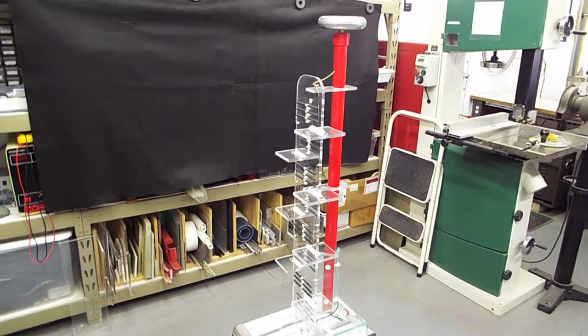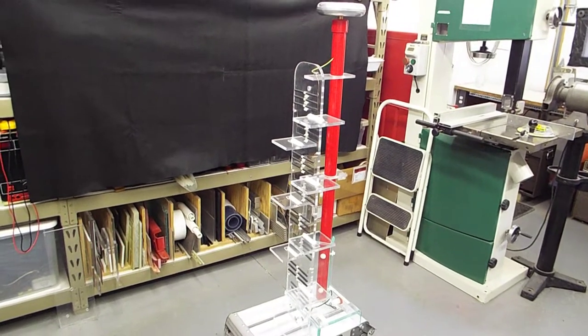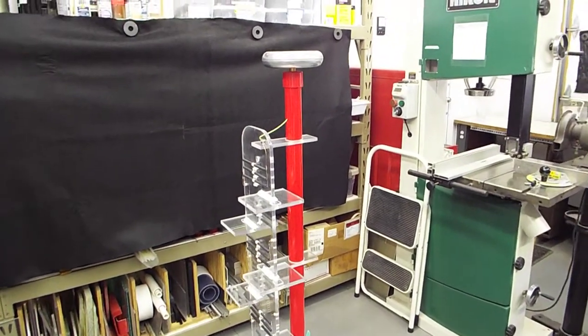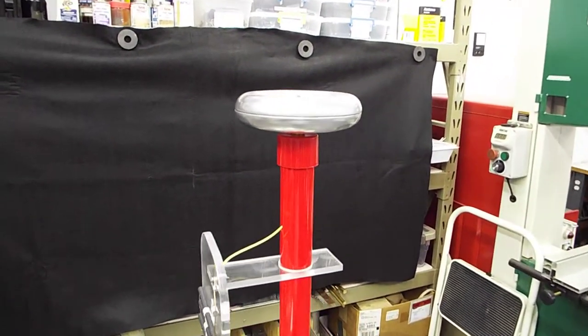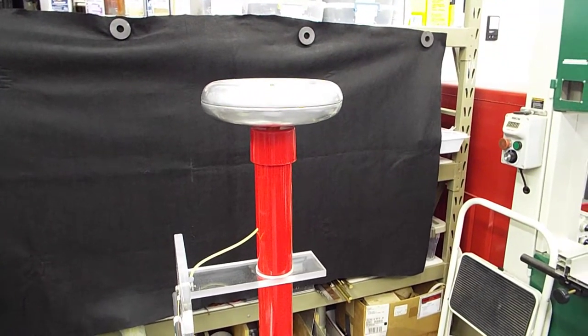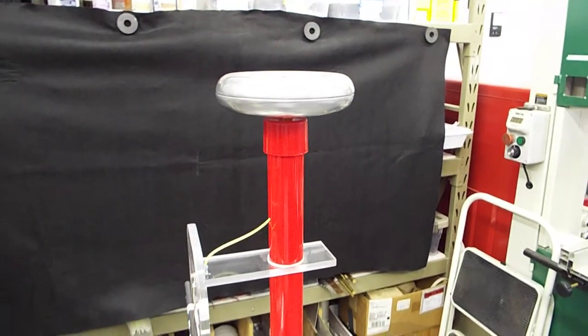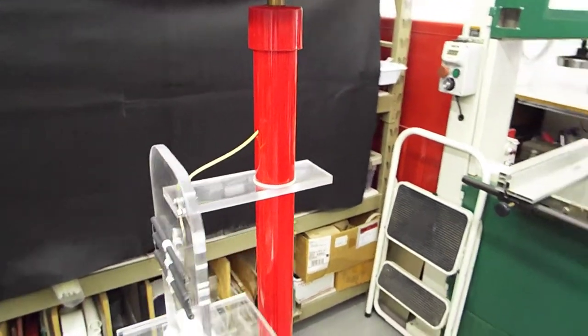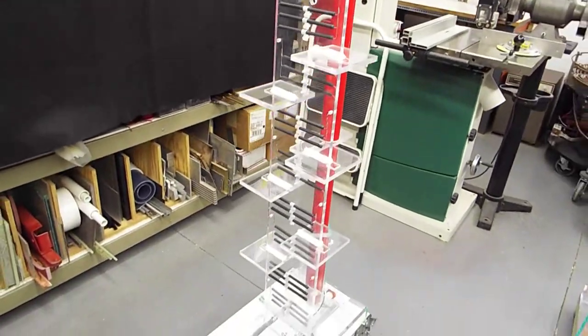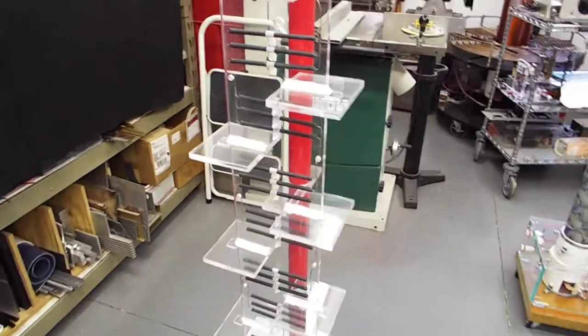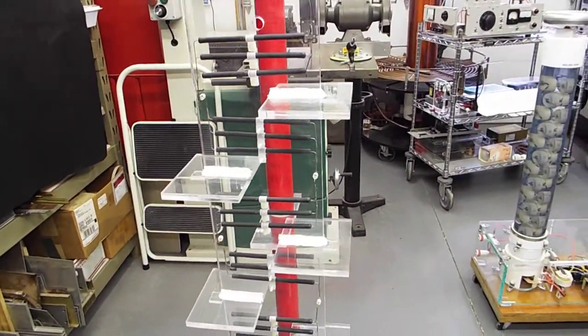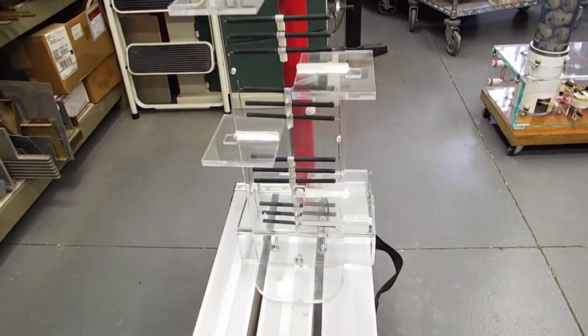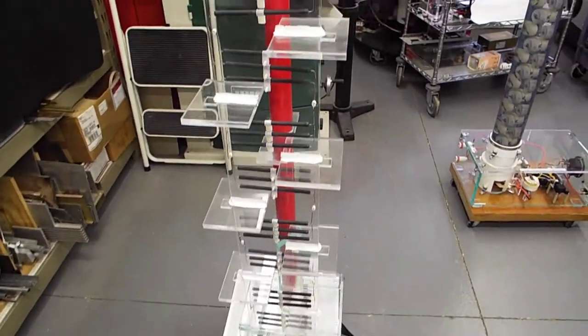This device here is the load resistance. It actually does two things: it forms a discharge terminal - you can see that on this toroid on the top - that's where the multiplier would discharge into. Then it's connected by this wire right here to this string of resistors which move down here. They're the black objects. There's 24 of them. They're connected in series-parallel, and these are not your normal resistors; these are high voltage, high power resistors.